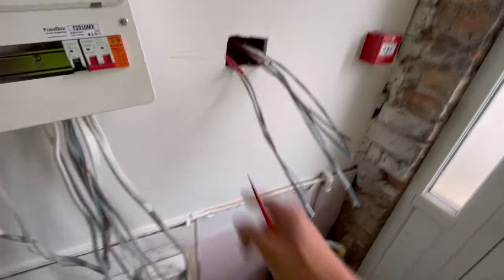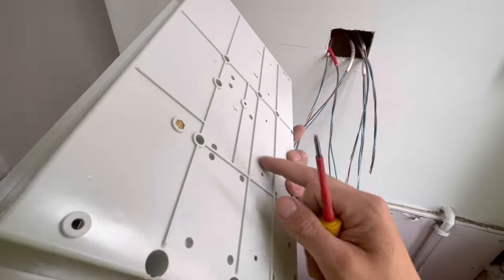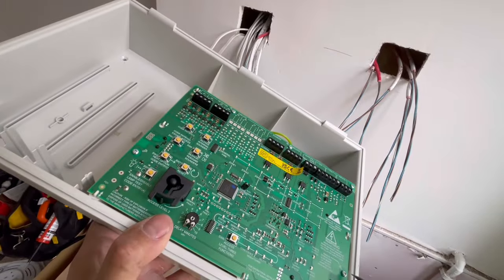1850. And then what I'm going to do is the consumer unit that we've got as well. So what I want to do is make sure that the switches come out at 1350. So I'm just going to mark the top of that. And then I'll leave that for now, and I'll just focus on this. So if I have that the same height, obviously I need my cable to come through the back there. So this is where I'm now going to cut out.